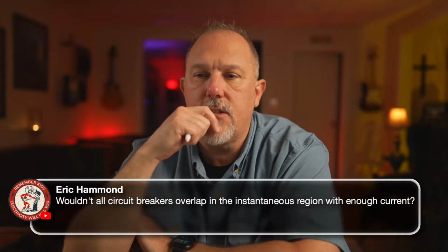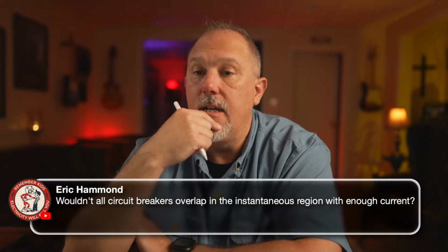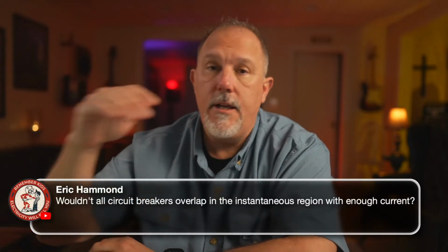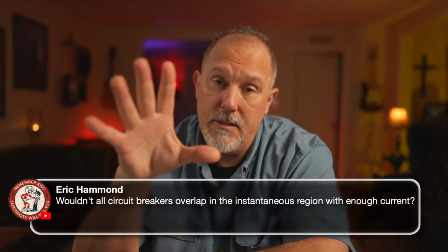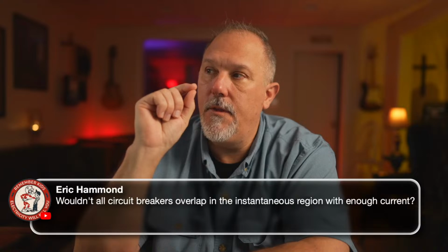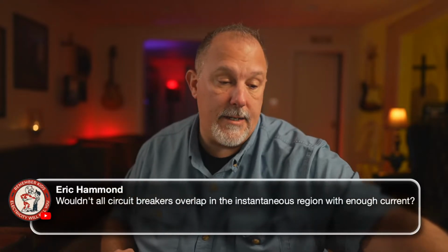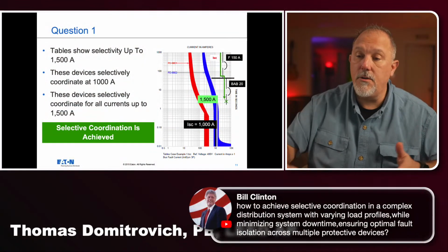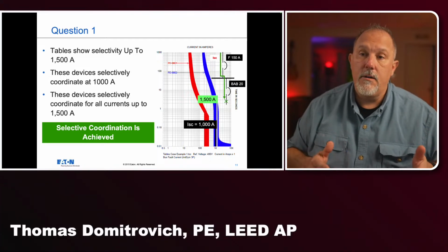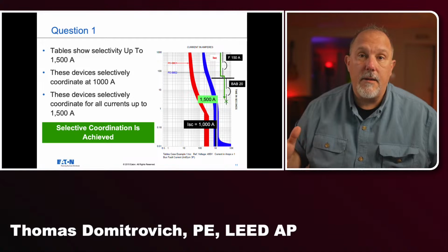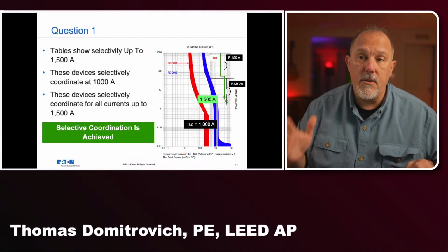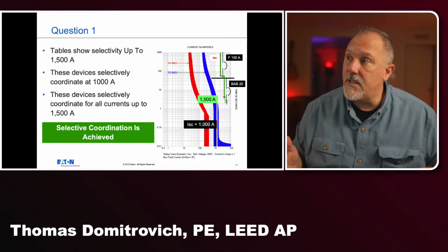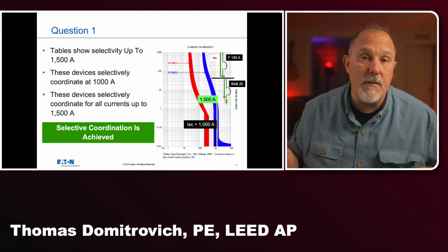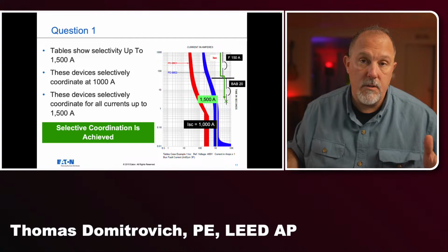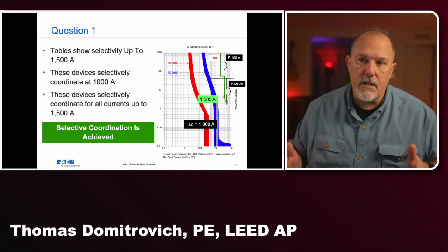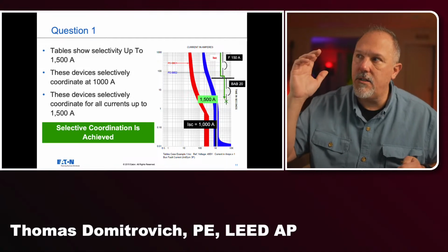Eric Hammond, wouldn't all circuit breakers overlap in the instantaneous region with enough current? Yeah, Eric. Again, don't think about it as an overlap. I run into this a lot. I call them artists. They're no longer engineers. If I'm just looking for separation of curves, I'm not doing engineering work. I've got to understand the available fault current. And in this case, these two curves do not overlap, yet I have a selective coordination issue. So we can't just think about selective coordination as pretty curves that shouldn't overlap.